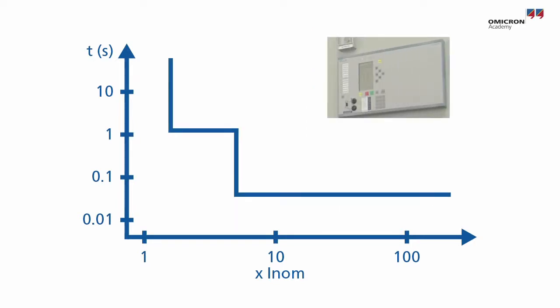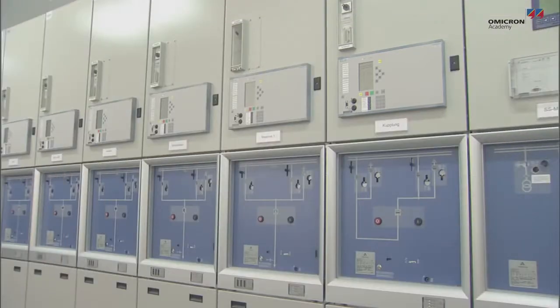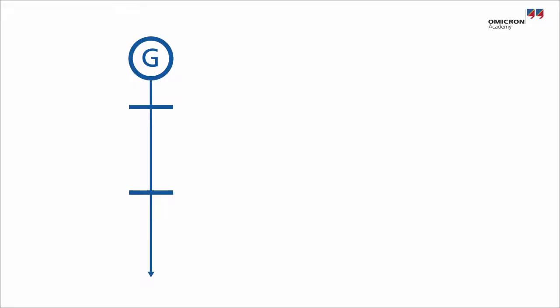Modern relays usually combine different curves within one housing. The complete protection system also includes elements residing in a number of other relays. All protective elements need to work together in order to form a selective system. For instance, when a fault occurs here, it should not affect the electrical supply of customers in the neighboring segment. Only the affected segment should be switched off.